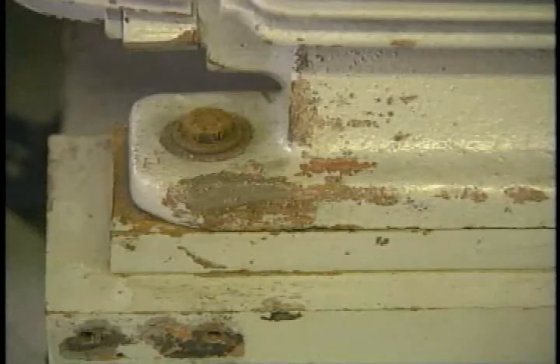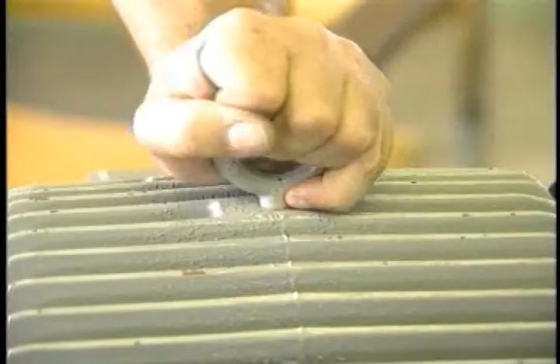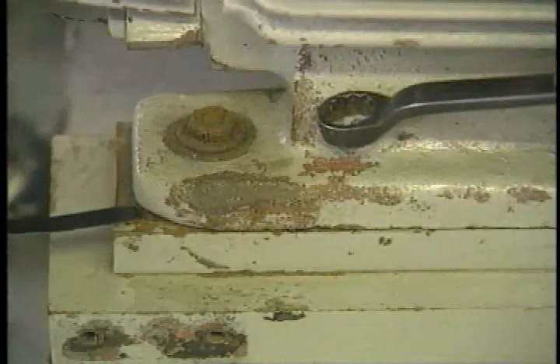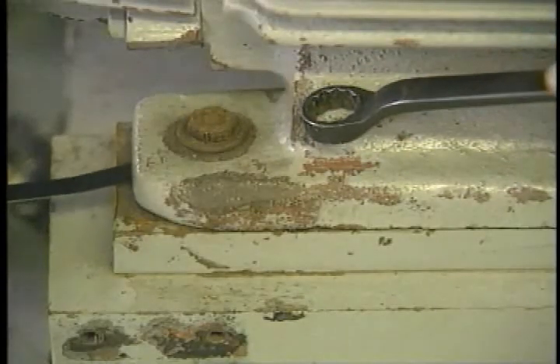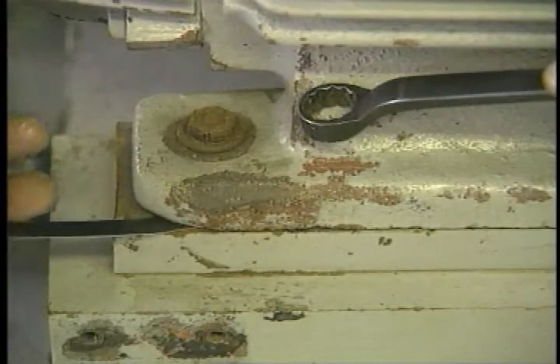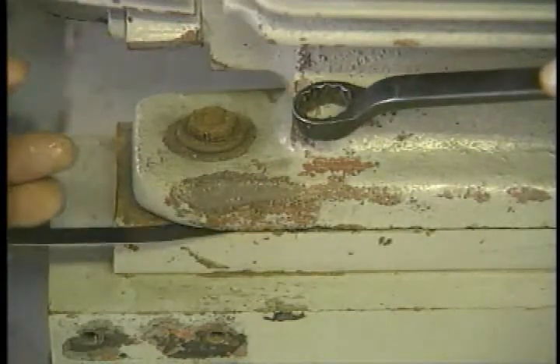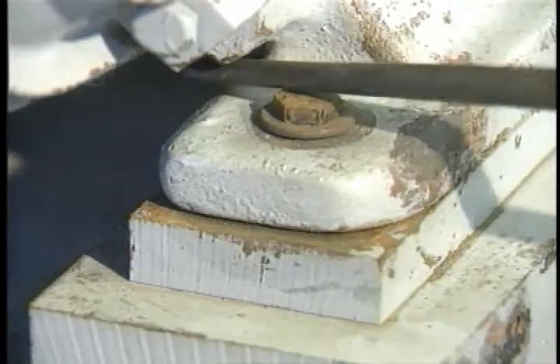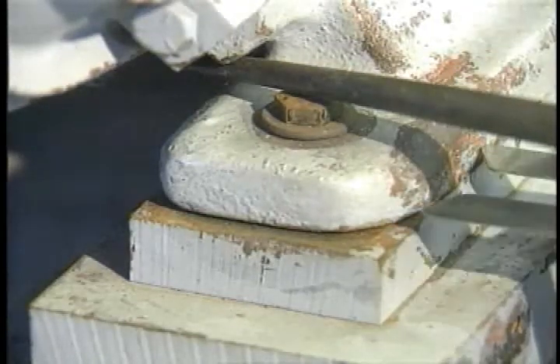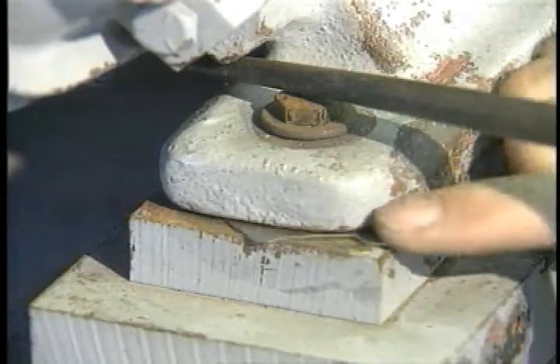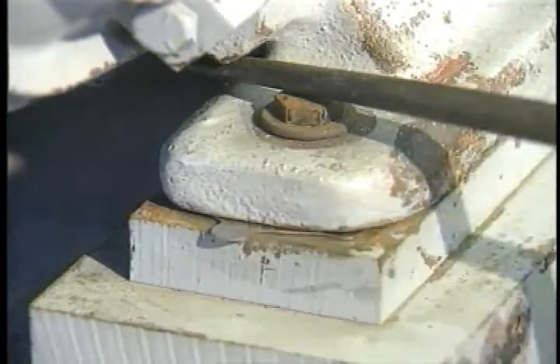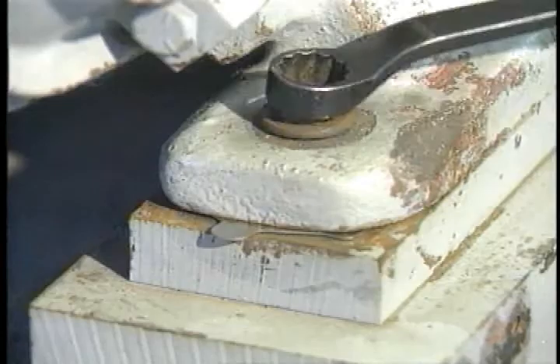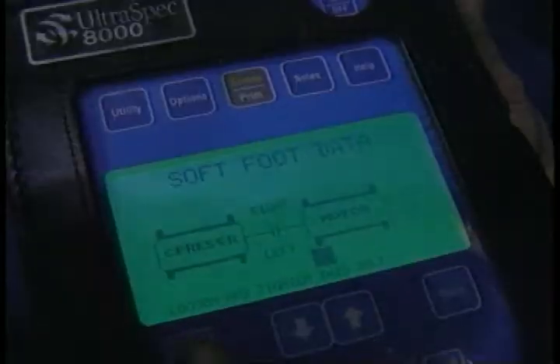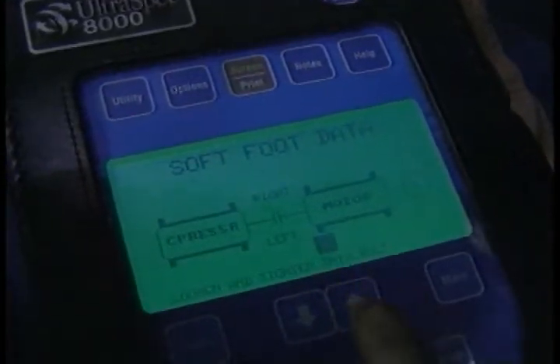All 4 feet of the driven unit must rest firmly on the base plate. First, try rocking the unit, and then try to run a single thin blade of a feeler gauge under each foot. If there is any movement or any clearance, add shims until the driven unit is solid. Pre-cut stainless shims should be used if they are available. Do not attempt to stabilize the unit simply by tightening down the bolts. If the bolts are loosened, the unit will shift positions immediately. This condition is known as soft foot, and it makes accurate alignment impossible.